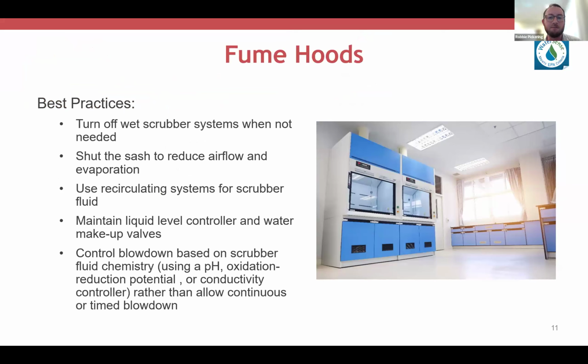Within wet scrubber systems, use recirculating systems for the scrubber fluid, and make sure that any level controllers or makeup water valves are functioning as intended. And then lastly, be sure to control any blowdown from these scrubber systems via a conductivity controller or pH controller, very similar to how you might do that on a cooling tower system, so that they're not just blowing down continuously.